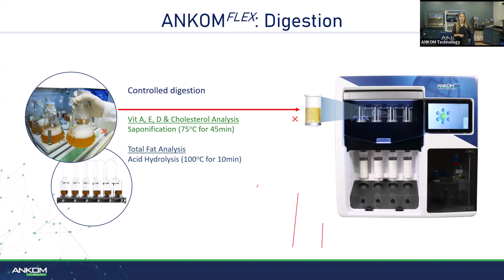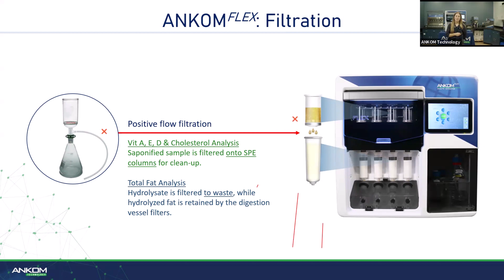Under positive flow filtration, there is a filter disc in the digestion vessel that the sample is filtered through. The saponified sample is filtered onto the SPE column for cleanup. The hydrolysate is filtered to waste, while the hydrolyzed fat is retained on the vessel filter, and then that is pushed onto SPE for cleanup. So the vitamin column will hold up your polar compounds and elute the analyte into your round bottom flask.